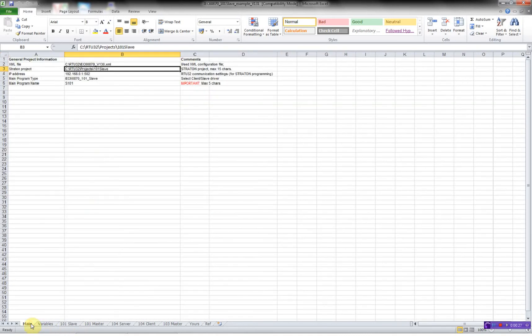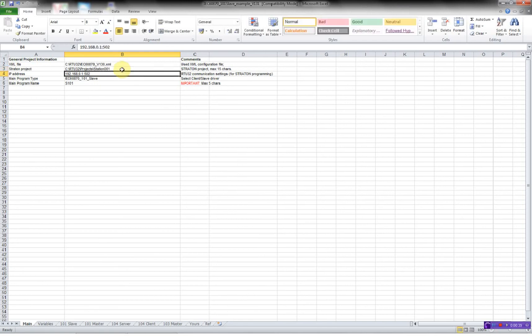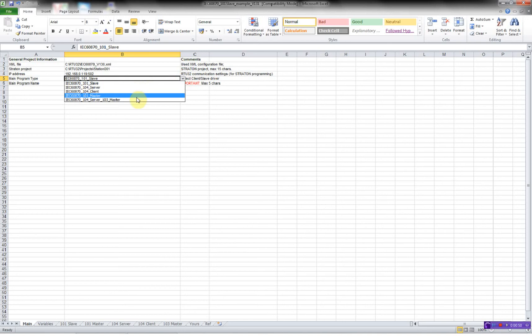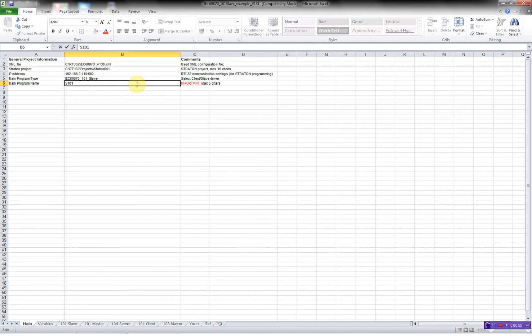First, go to the main worksheet and enter where to save my project on the PC. We'll call this station like this, then configure the IP address of the RTU32. Here I can choose the program type — 101, master or slave — in this case it's a 101 slave. Then I'll give my station address zero. Now I've done the configuration in the main worksheet.